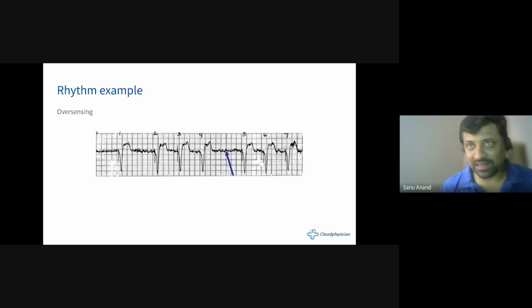So that is why, when I said keep the sensitivity at half of the sensing threshold you discover initially, and not one-fourth or one-third. If the pacemaker setting is too sensitive, then it'll pick up everything: your ventilator pushing in air, every time you move the patient, or even the carotid beating or muscle twitches. Everything can get picked up, and the pacemaker will not fire an impulse at all.